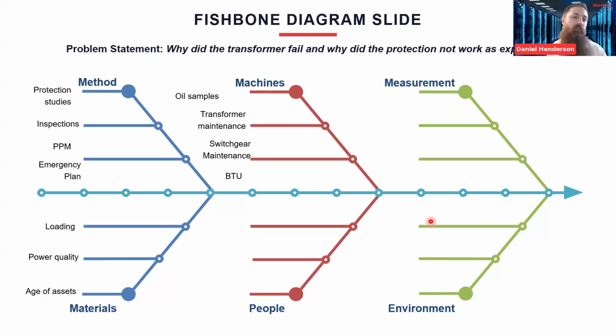From the third-party contractor perspective, as part of the onboarding process, there was verification of their competency assessments, the framework that they apply. On the report, it's things like, were they trained to do partial discharge testing? They had their certificate of competency for that. Likewise for thermography, and you also got the calibration date and number for the actual test equipment that they were using.